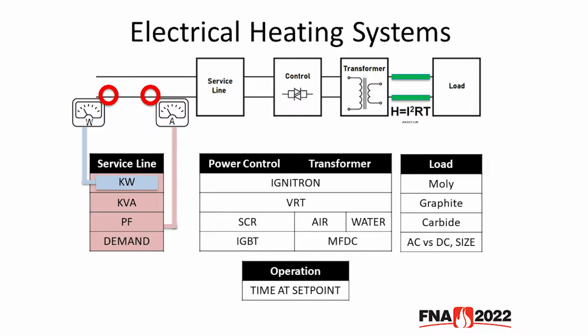After the transformer, everything is essentially a heating element. If you look under the green cables here, it shows Joule's law, which states that heat is proportional to current squared. One of the value propositions we'll cover later is reducing this high current circuit outside the furnace to improve efficiency. The load is then energized.